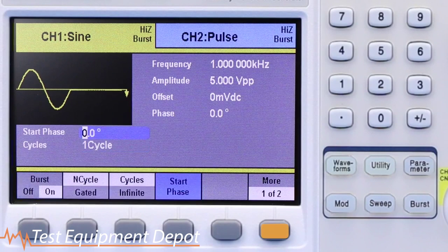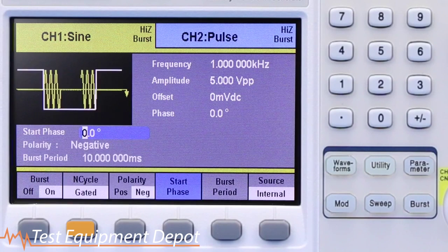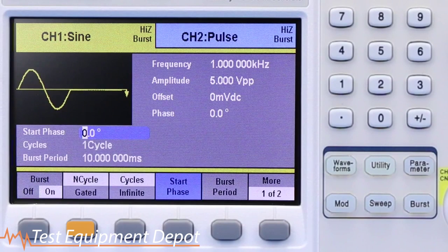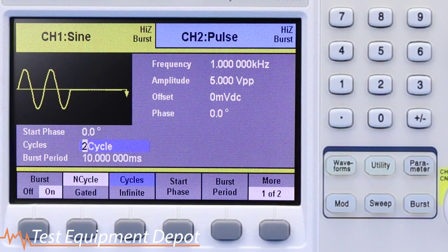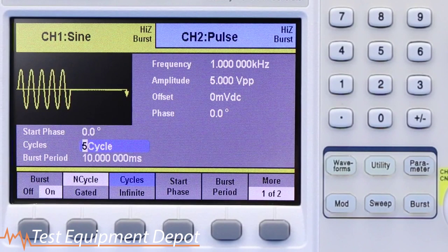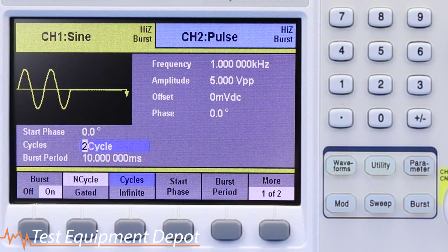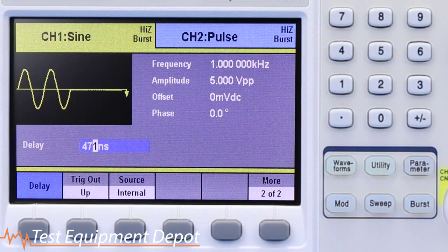To use a specified number of cycles to burst, make sure NCycle is selected. Then set the number of cycles desired and burst delay if needed. When the manual trigger button is pressed, the generator will output the burst mode waveform.